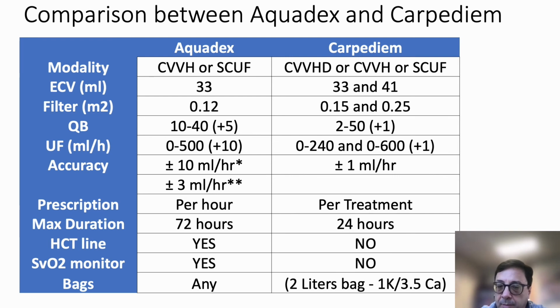Ultrafiltration is similar. You can calibrate by 1s in Carpe Diem versus by 10s in Aquadex. The accuracy is more precise in the Carpe Diem. And the prescription is per hour in Aquadex. It's per treatment in Carpe Diem, so you have to figure out how many hours you're going to do the therapy. The max duration of therapy in the Aquadex is 72 hours versus 24 hours that you have to change out the circuit in the Carpe Diem. The Aquadex has a hematocrit line and an SVO2 monitor, and the bags that you could use for replacement in Aquadex are any bags you have available, whereas you have to use the 1K 3.5 calcium bag in the Carpe Diem.